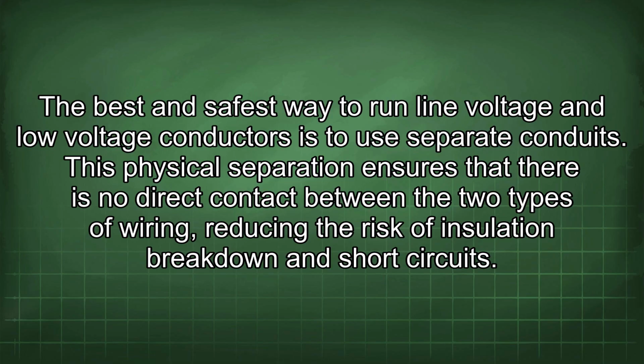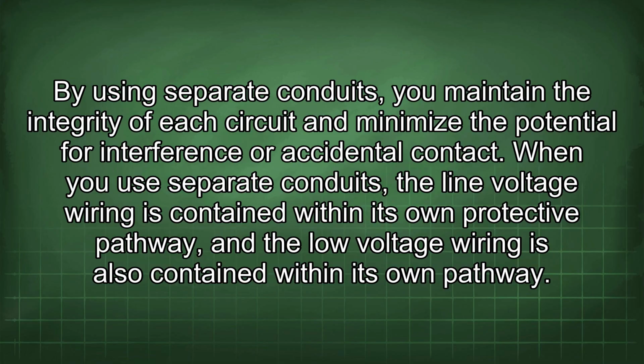The best and safest way to run line voltage and low voltage conductors is to use separate conduits. This physical separation ensures that there is no direct contact between the two types of wiring, reducing the risk of insulation breakdown and short circuits. By using separate conduits, you maintain the integrity of each circuit and minimize the potential for interference or accidental contact.